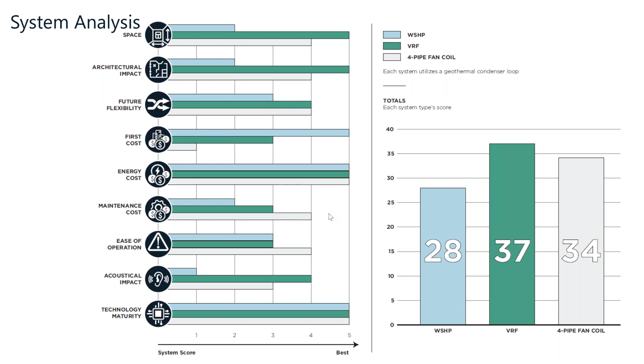And that became a very good component of a design, versus say, some existing building infrastructure out there that has a packaged rooftop unit that serves all classrooms and the air is recirculated. That has a completely different approach to it when you talk about health in a building and filtration and isolating individual rooms. So this system allows us to do that and treat any individual room and not recirculate or redistribute contaminants from one classroom throughout the building, which was pretty nice.